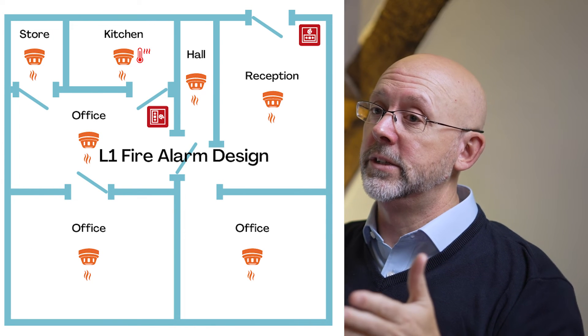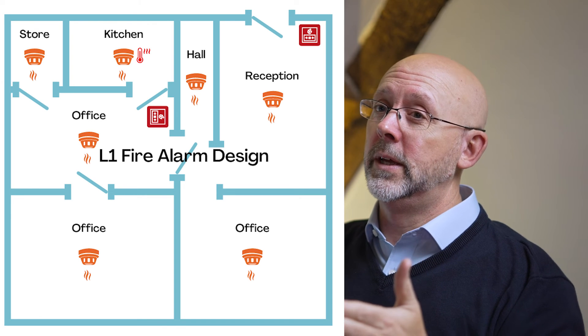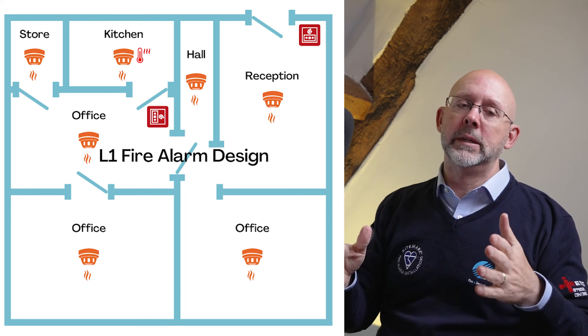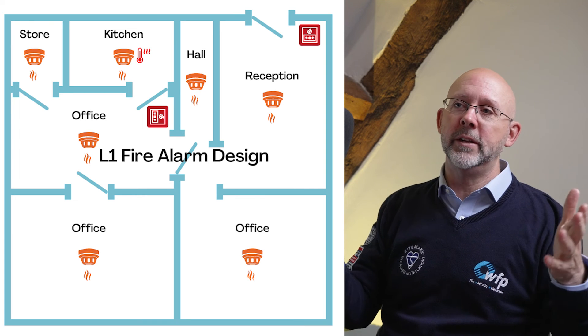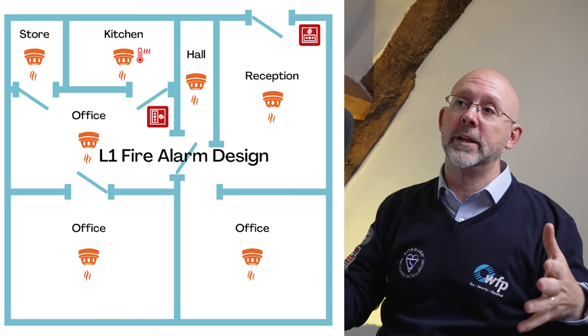L1 is every room larger than one metre squared having a smoke detector, including large cupboards. It's quite intensive and doesn't happen that often, but a fire risk assessor would specify it for high-risk buildings with many occupants where the earliest possible warning is needed, since smoke is the primary life safety concern. In the UK, around 98% of systems fall into L1 through L5, with L3 being the most commonly used. However, you won't know which category applies until the fire risk assessment has been completed.